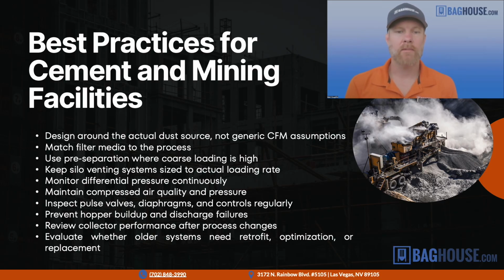Filter media is extremely important. Depending on where in the process you are, what type of material you're collecting and conveying, and the process parameters, heat and whatnot, the filter media can make or break the performance of your dust collection system. So temperature, moisture, abrasiveness, particle size, all these things we talked about can influence the correct filter media for your dust collector. We may even want to have a cyclone pre-separator in front of it.